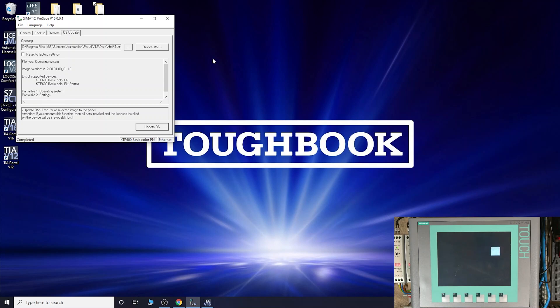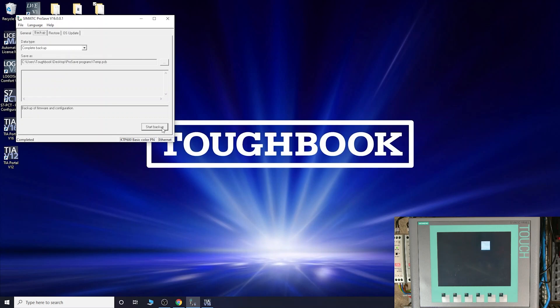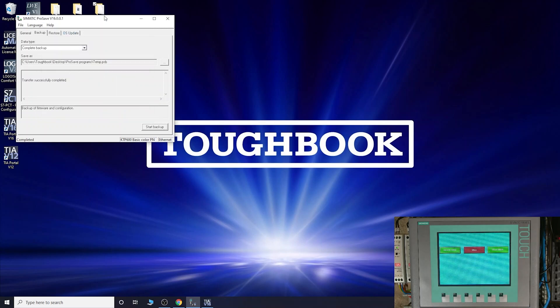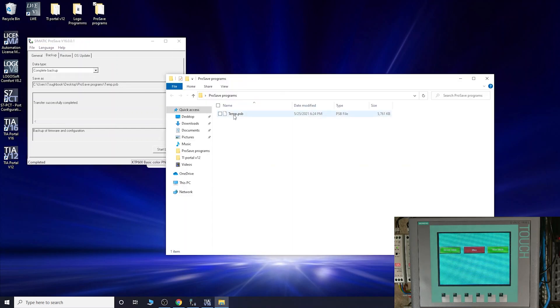First thing - when you do an OS update it's going to wipe everything off, so before we do that we need to back up. Click Backup and then Start Backup. As you can see it will start doing the backup - that takes quite a bit of time, so I'll pause here. Here we are - done. I've got my file here in the ProSave programs folder. The program has been backed up, roughly about 5 megabytes. We'll name it KTP 600. You've now backed up your program, ready for a rainy day.